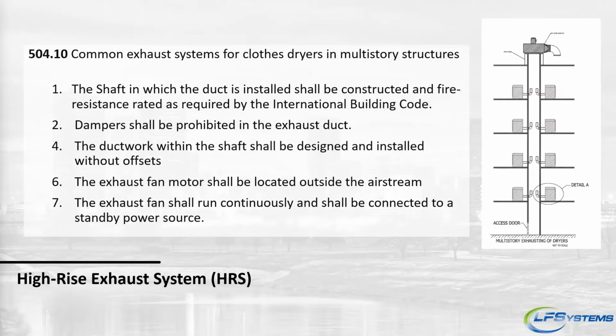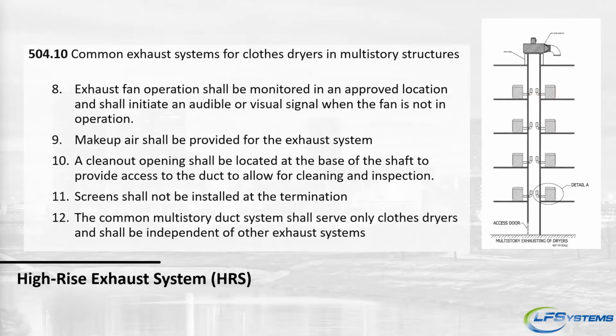A few other things to keep a look at. The fan must be monitored where you have an audible or visible alarm. So it has to be connected to something that notifies you if the fan is not operating. Makeup air shall be provided for any exhaust system in a building. So you've got to make sure that if you're sizing that fan for a vertical shaft, you must provide makeup air.